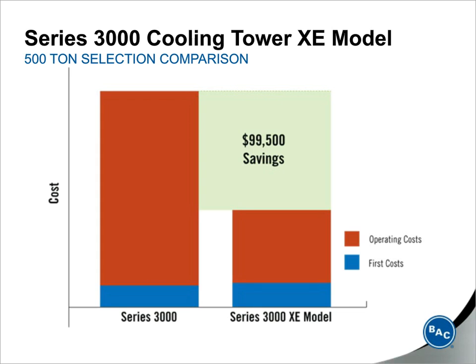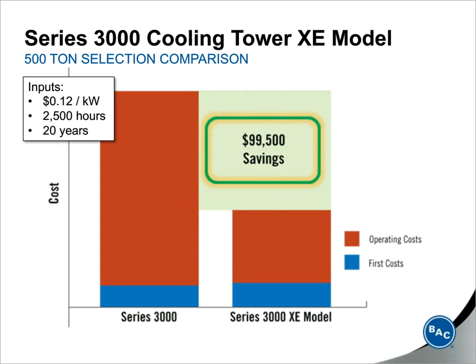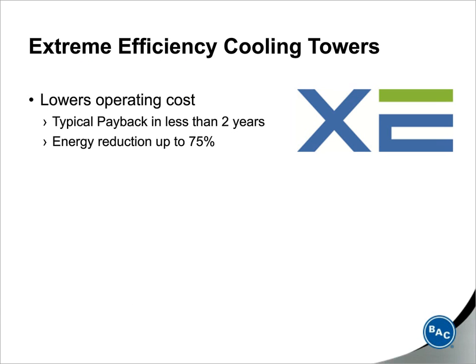So at 12 cents per kilowatt, 2,500 equivalent full load hours in a year, the extreme efficiency model over a 20-year life of the unit can save $100,000 when you compare it to the unit with the lowest first cost. In general, the extreme efficiency cooling towers can lower operating costs. They can offer a payback generally in less than 2 years, and they reduce energy by up to 75%.